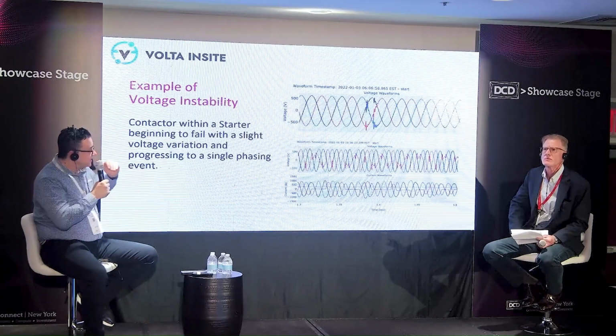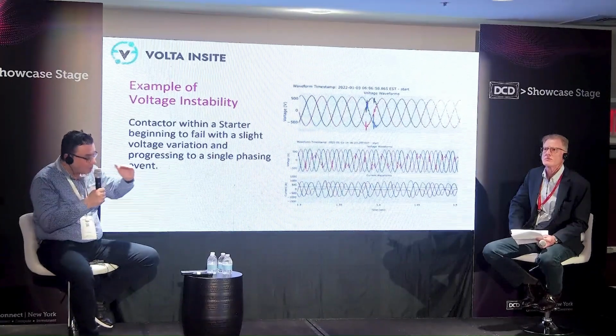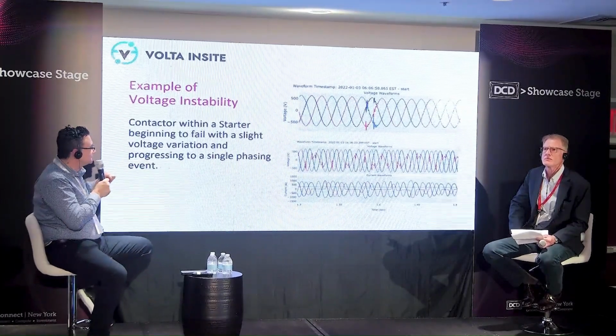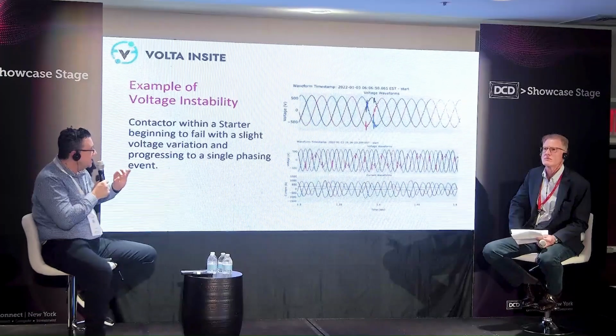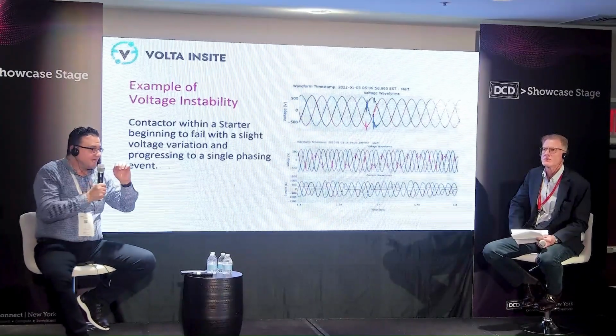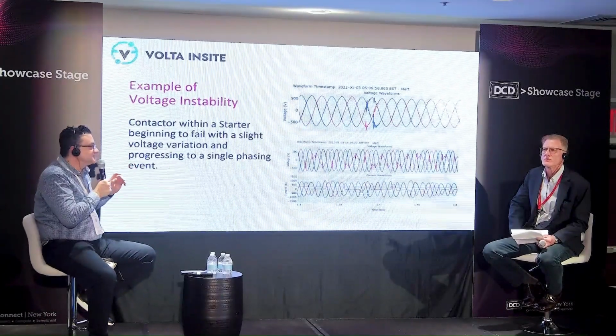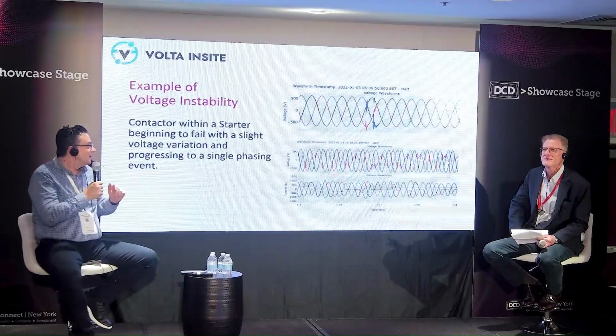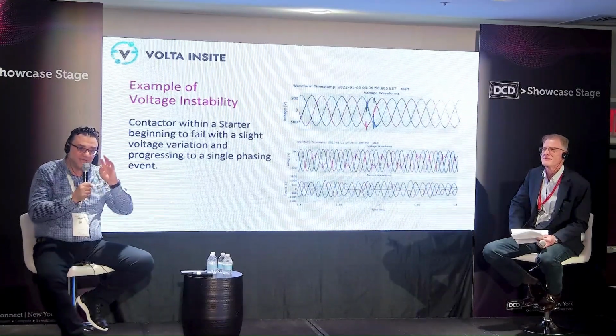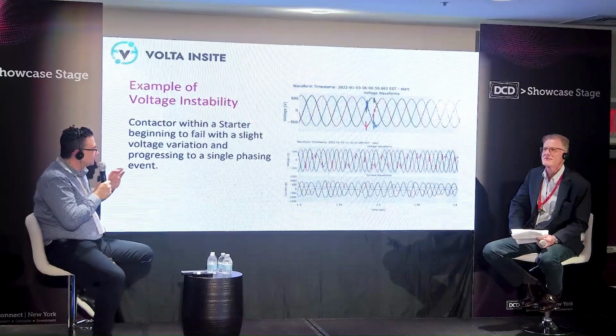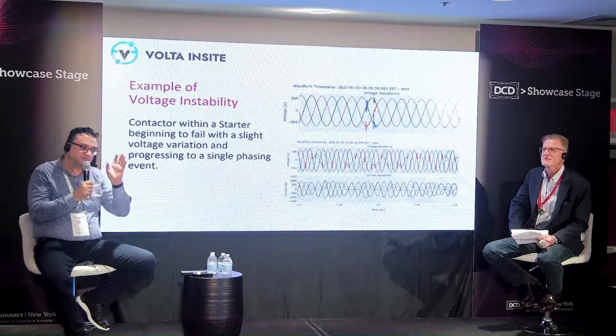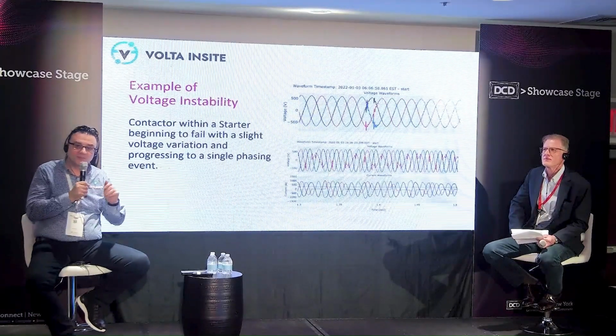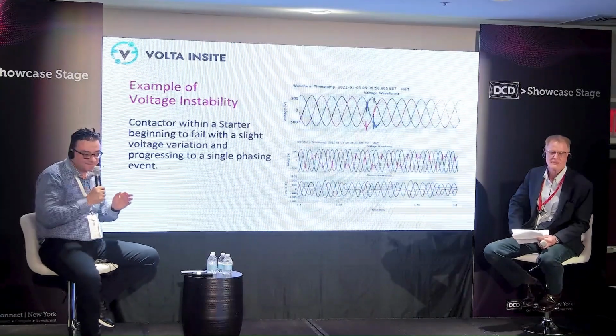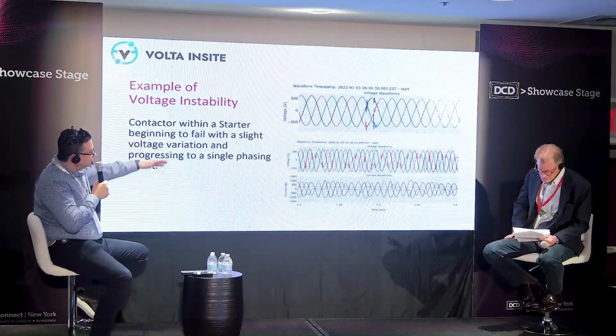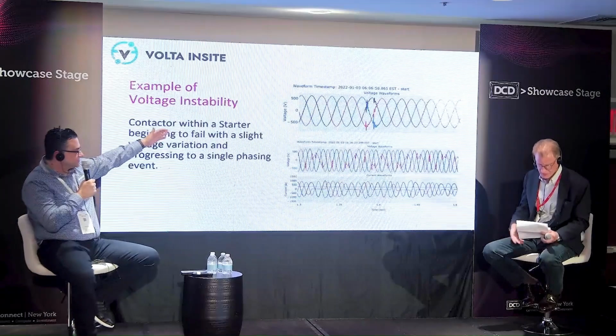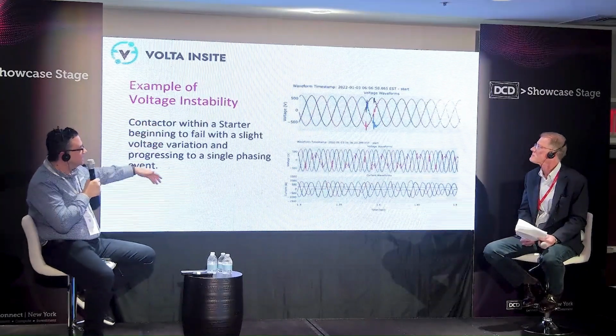Because we're always capturing these waveforms, we can see slight anomalies that your typical DCIM is never going to capture. If we have these anomalies captured, we can go back and say, well, this is potentially a bad breaker or a bad contactor starting to fail. This is a good example of a contactor that's actually failing within one day.